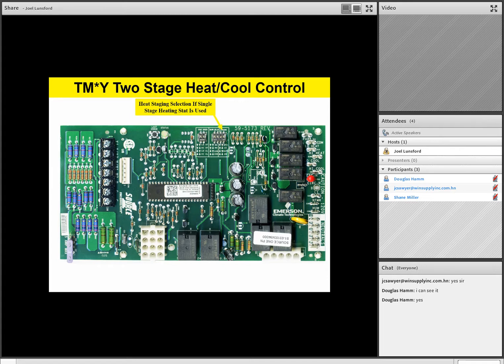So you can still get staging capability with this board. To my knowledge, I don't know of any other manufacturer that does this. So this is something unique to the Johnson Controls Champion product. As far as I know, no other manufacturer does this. But it allows us to have intelligent staging on our control board if we're stuck with a single stage thermostat. Now team, we always recommend that if you have a two-stage product, be sure and have a two-stage thermostat on there. But if you're stuck with a single-stage thermostat, we can still give you some really nice staging function with these staging dip switches, either auto, 10-minute or 20-minute staging, but we recommend putting it in the auto position. That way the board makes some intelligent decisions on staging.